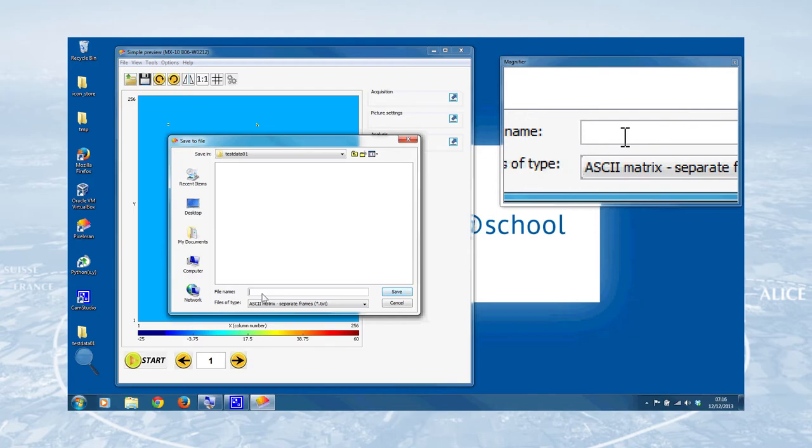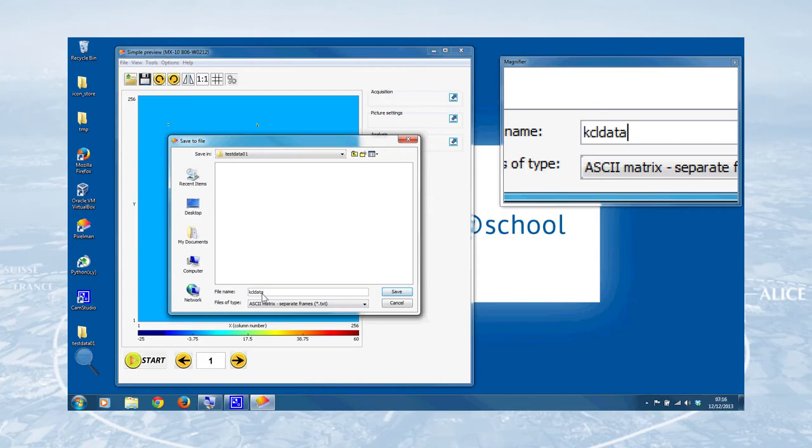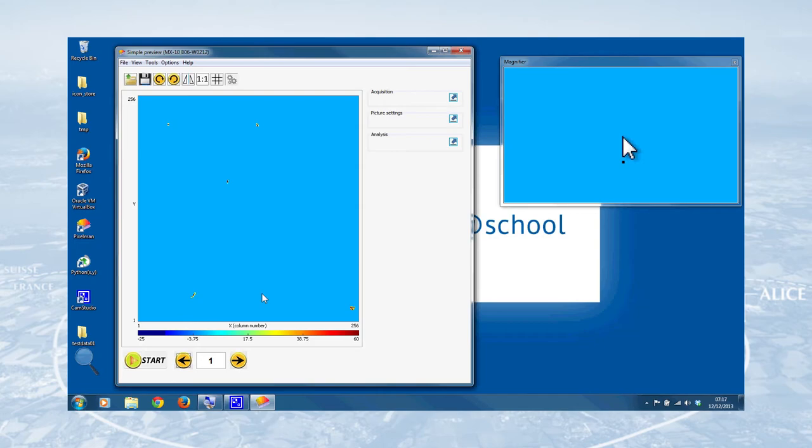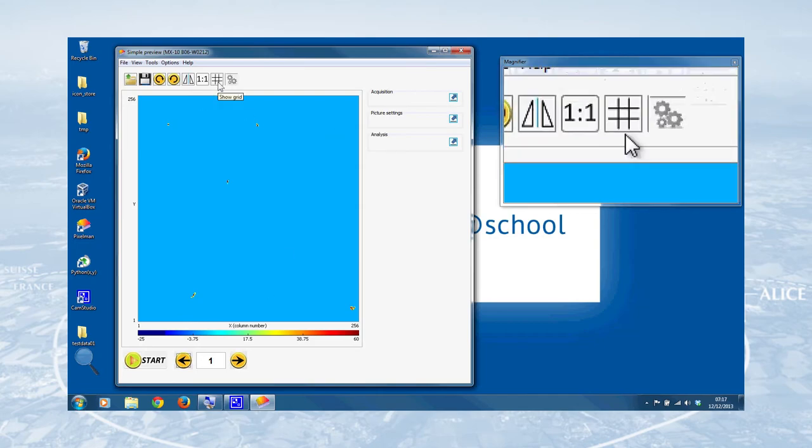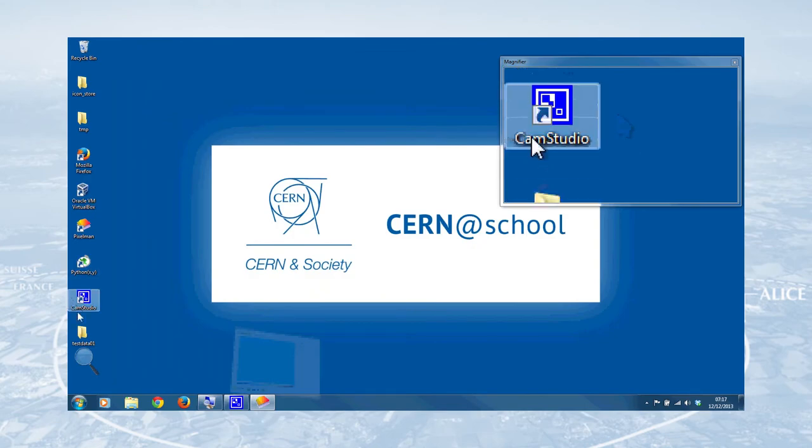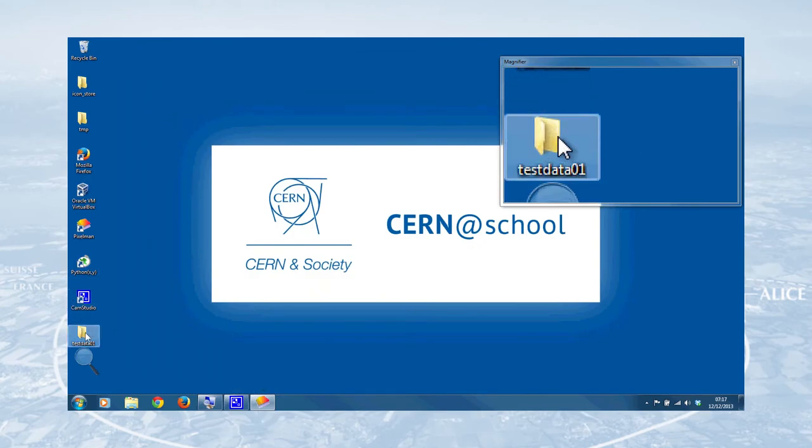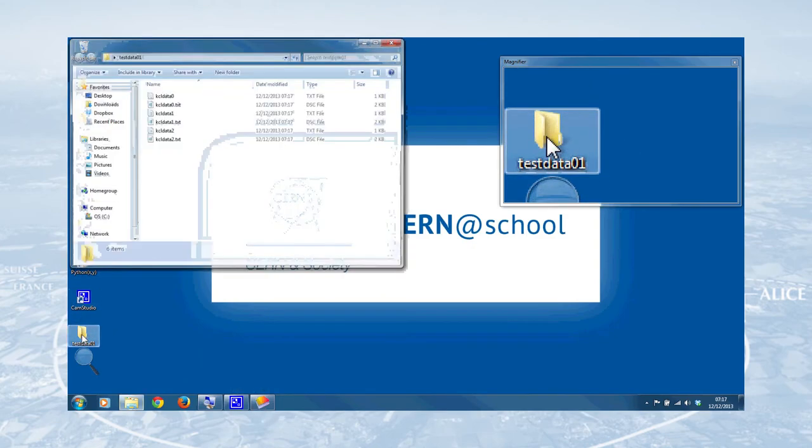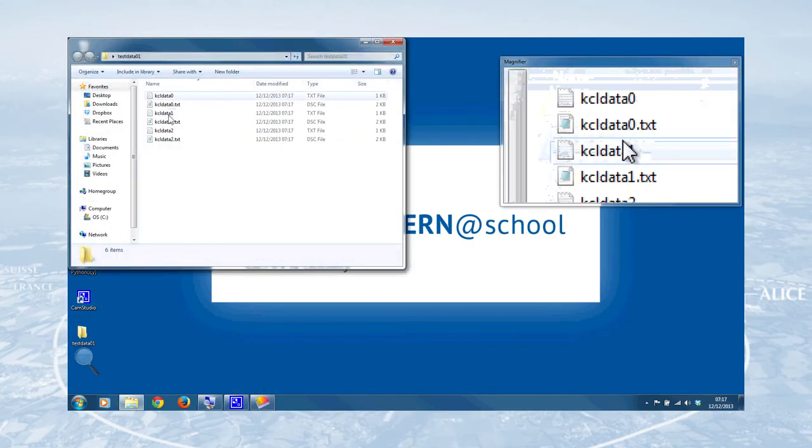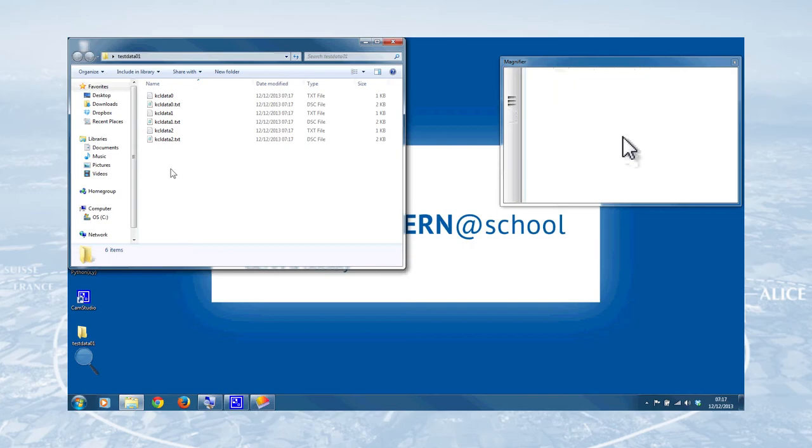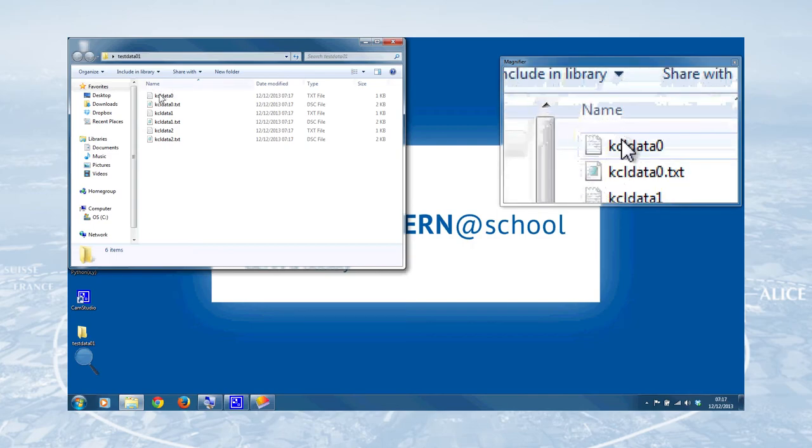We can double click on that. And then enter a base file name like KCL data, for example. Pixelman will add the .txt extension, which makes it a text file. But there's also another file produced with each frame, the .txt.dsc file, which contains the detector settings. But we can look at those in a bit. So I'll just click save there or press return. And that will have saved the data. And before we close Pixelman, we can check that it's all worked by going to the test data 01 folder on the desktop. And lo and behold, three frames, six files that we can now inspect.